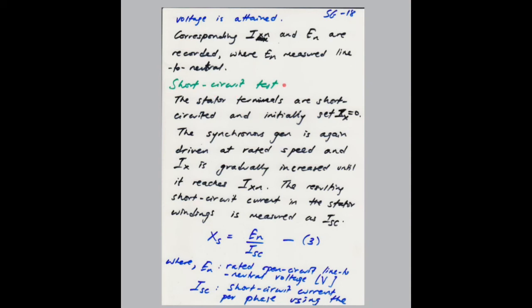The second test, which is the short circuit test, requires more safety precaution, because obviously you're applying a short circuit to the stator of the machine, right? It's dangerous, because high current will flow in the stator. So the initial precaution that you need to make sure of is that you set your field current to 0 before you start the test, right? Again, you will drive your generator at rated speed, and you will gradually increase Ix until you reach that nominal value Ixn, which you've measured from the open circuit test, right? The nominal value of your field current.